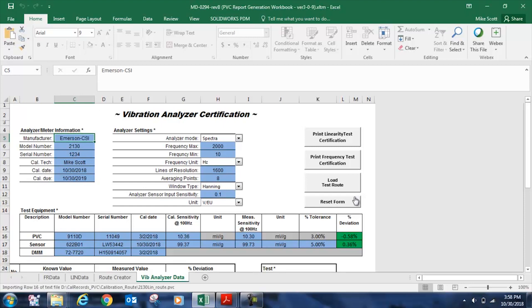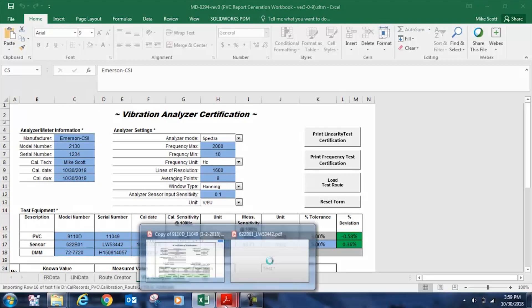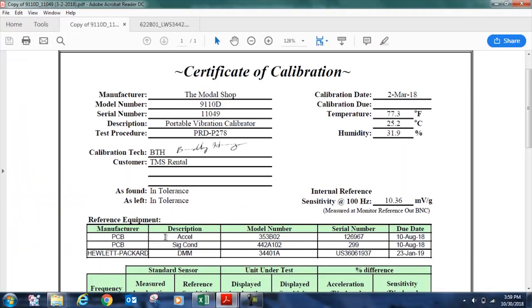Now that we have all that information documented, we need to document our 9110D, which is shown here. We used model 9110D, serial number 11049, which was calibrated on March 2nd, 2018. And at the time, it was calibrated at 10.36 millivolts per G for the reference accelerometer that's inside the unit. You can find that by looking at your calibration certificate, which is A2LA accredited for your 9110D.